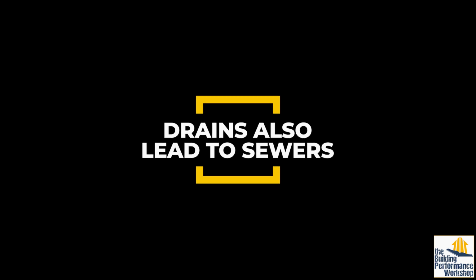Also, the condensate drain. Because we've got this wet coil, condensate is being created by that. We're supposedly draining that water out somewhere. So this sewer gas smell that we're worried about could be coming from a condensate drain that doesn't have a P-trap built into it. That might have occurred to some people.